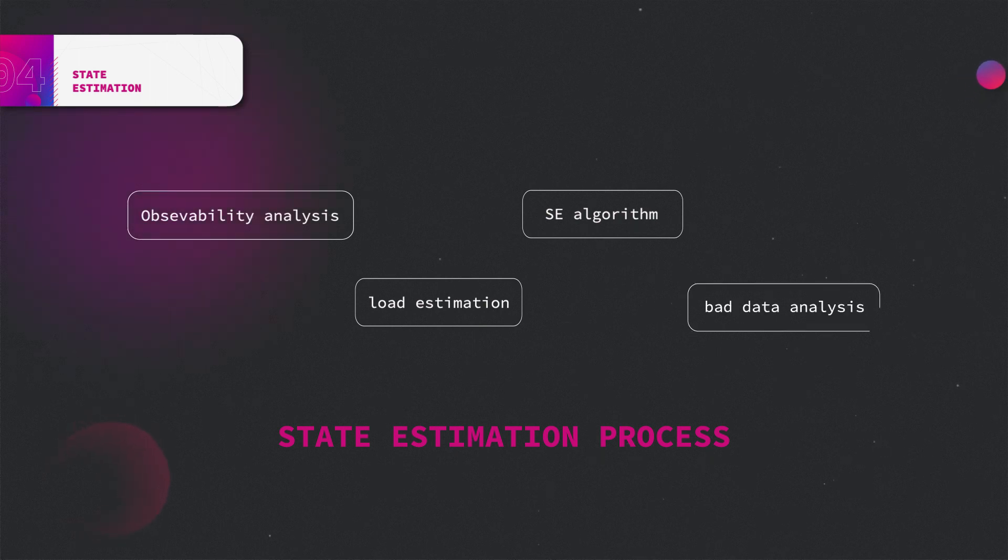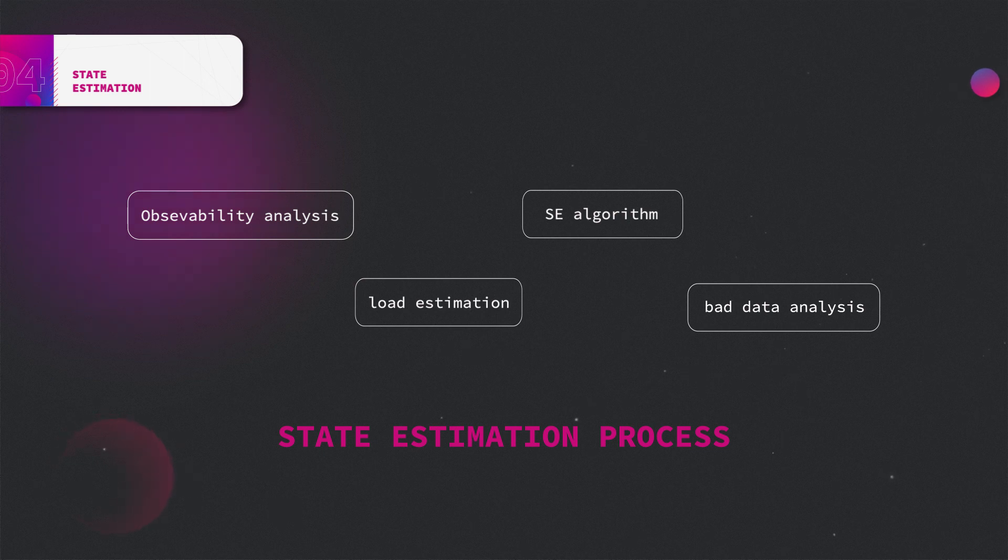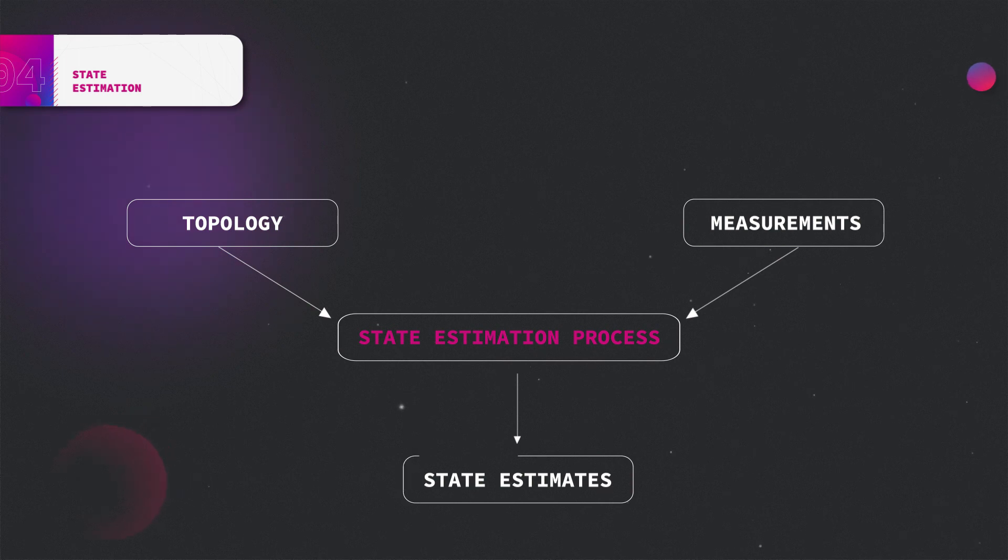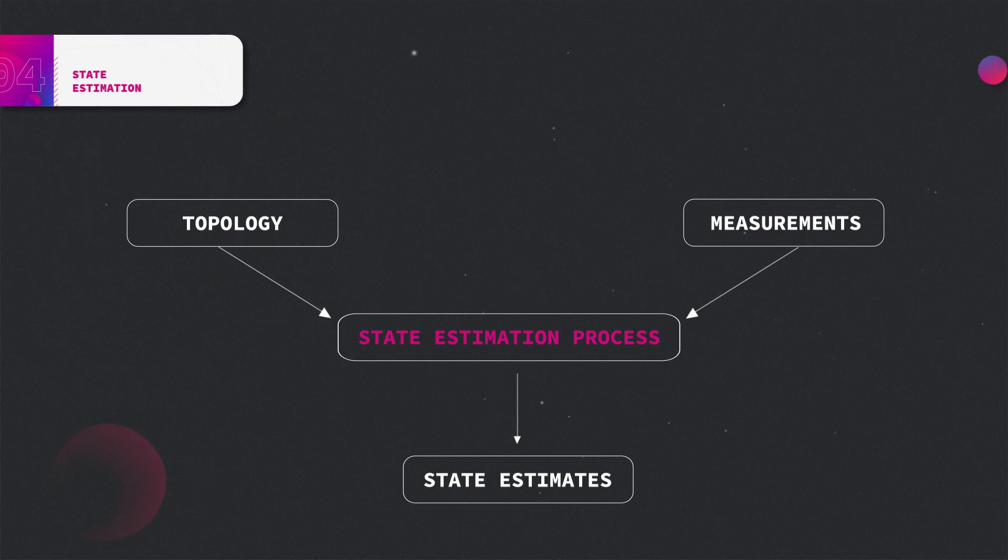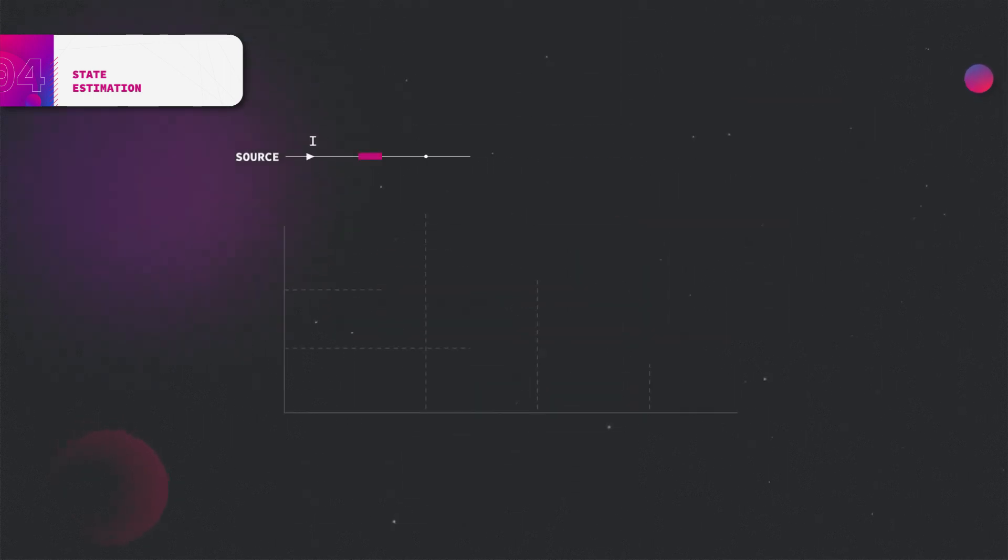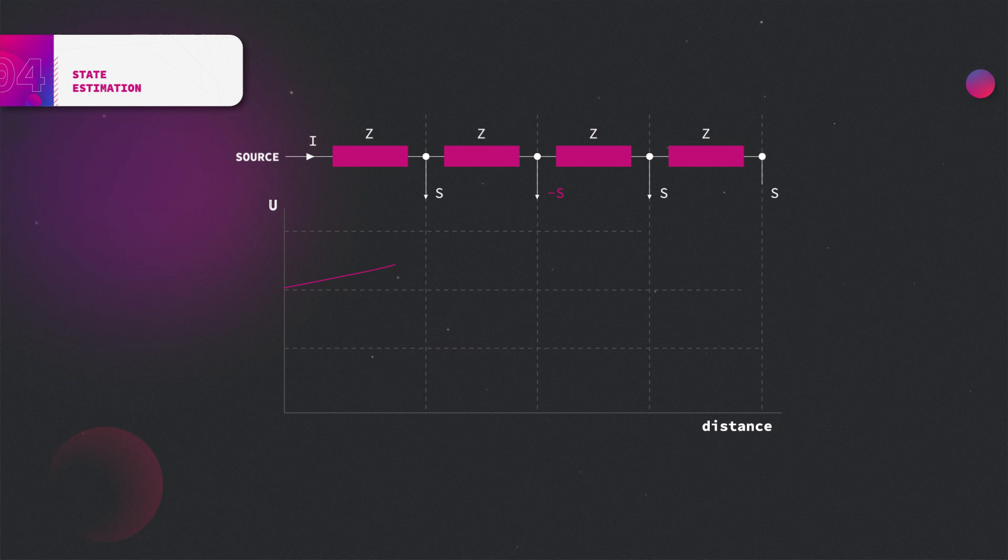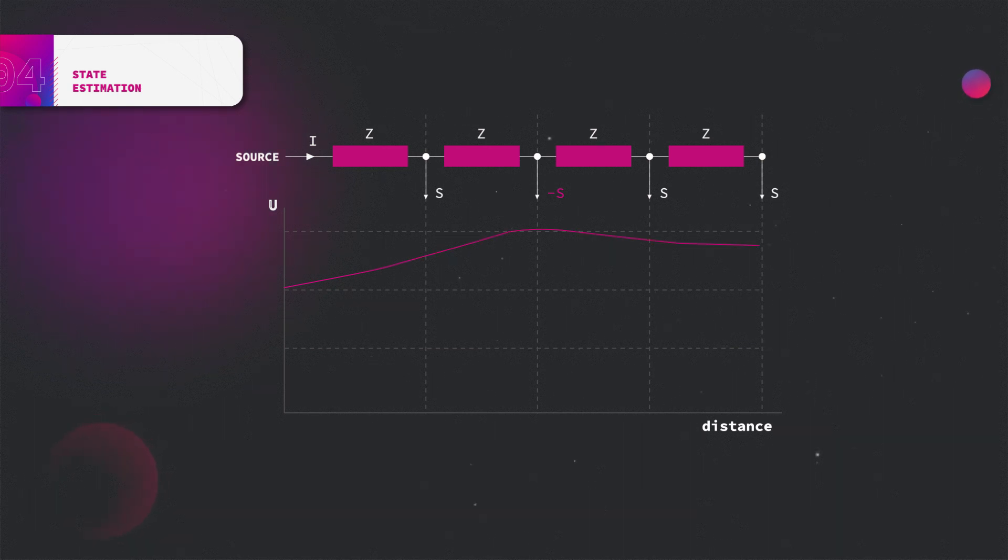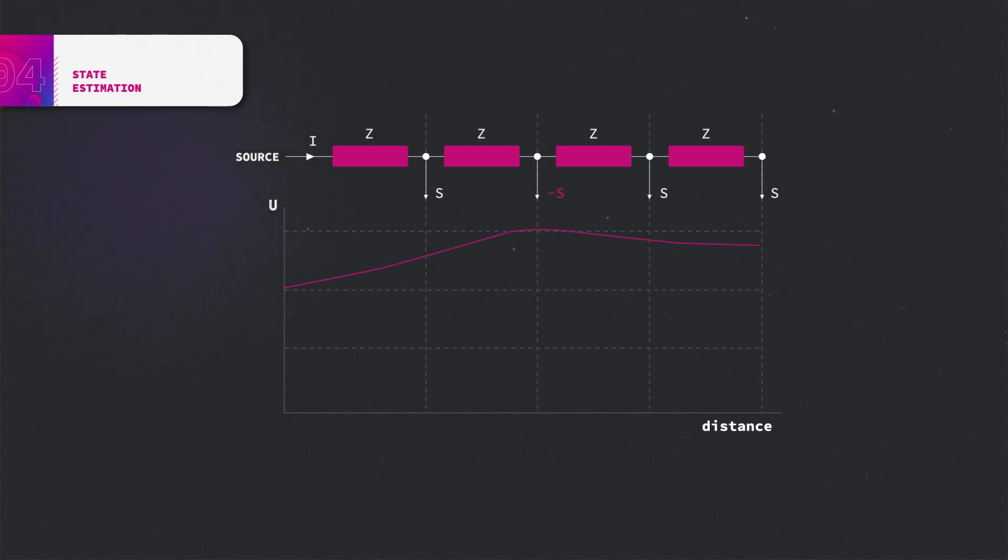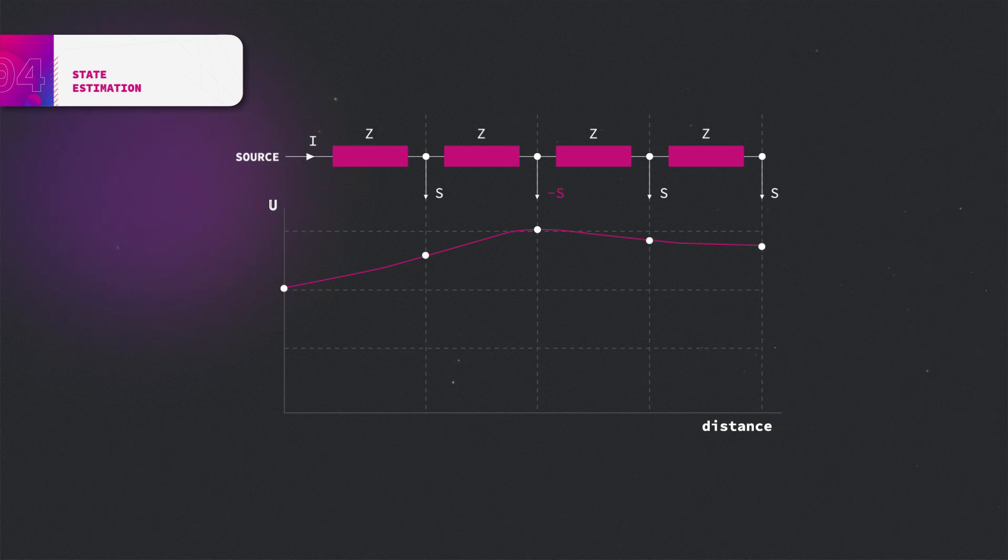Possible errors are being neutralized in the estimation process. In the end, the estimated state of the network is the output of the state estimation process by the means of defined state variables. As mentioned before, the vast majority of state estimators utilize voltage amplitudes and angles as their state variables. Nevertheless, it could also be variables of other types such as current or power. After the estimation process is done, the voltage at each bus of the network is thus defined.